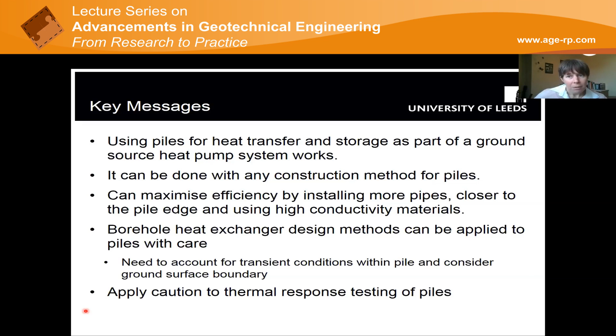If we want to maximize the efficiency of our system, we want to install as many pipes as we can, reasonably speaking, and make them as close to the pile edge as possible, i.e. put them on the pile cage, steel cage probably. If you can, use high conductivity materials, but it's potentially difficult, we appreciate that. There are existing methods for design of other vertical ground heat exchangers like boreholes, and we can apply them to piles with care, with some adjustments, but we need to account for the fact that the pile is transient, and we need to think about what happens at the surface of the pile. And while we can thermally test piles, we need to be quite careful about that as well, and how we interpret it.